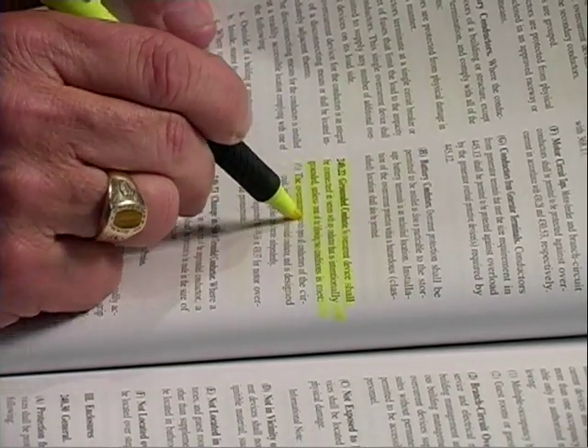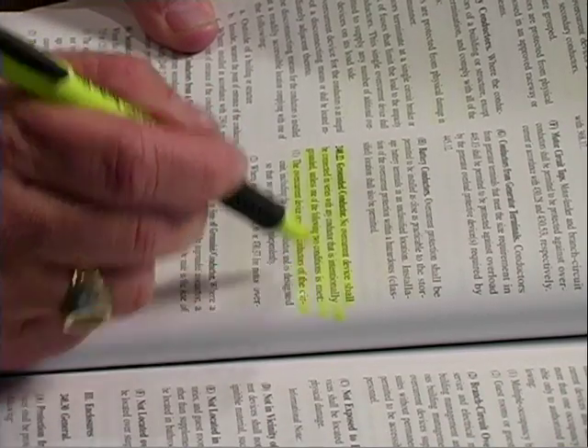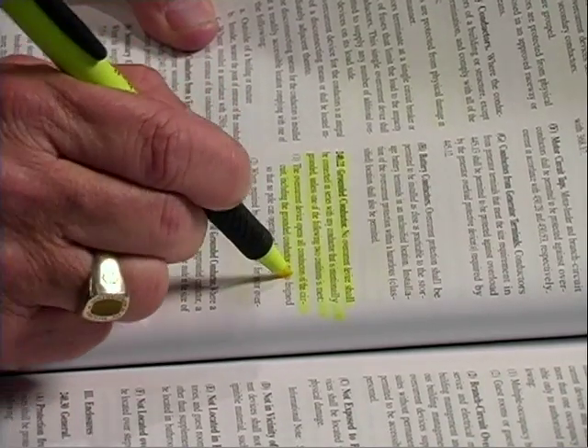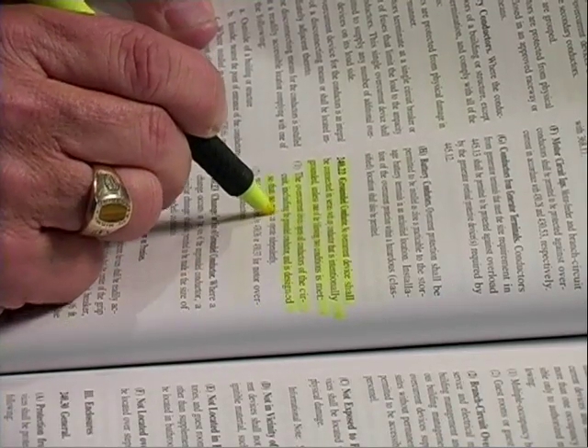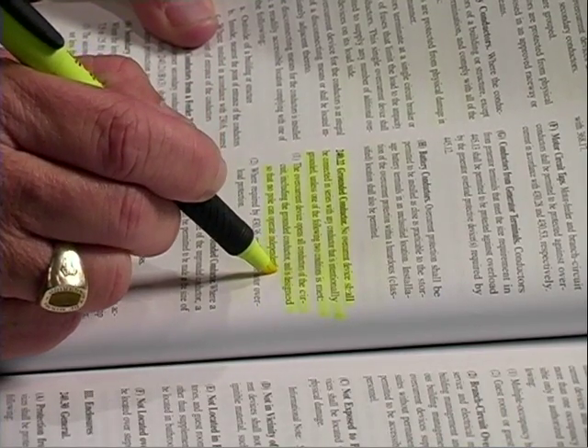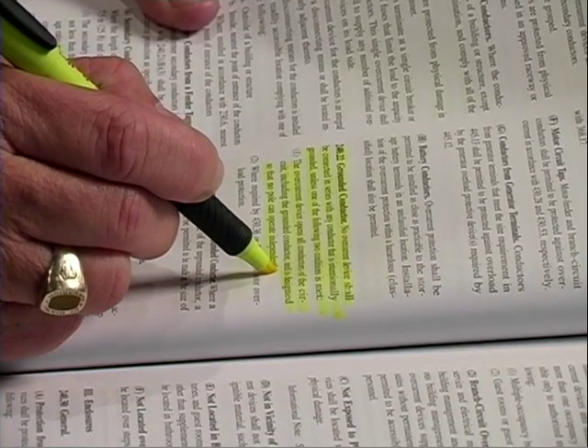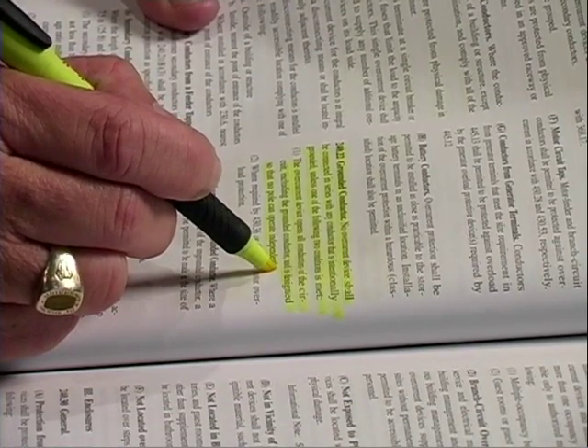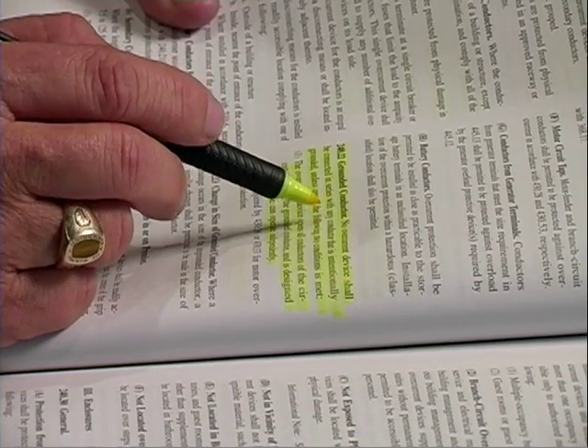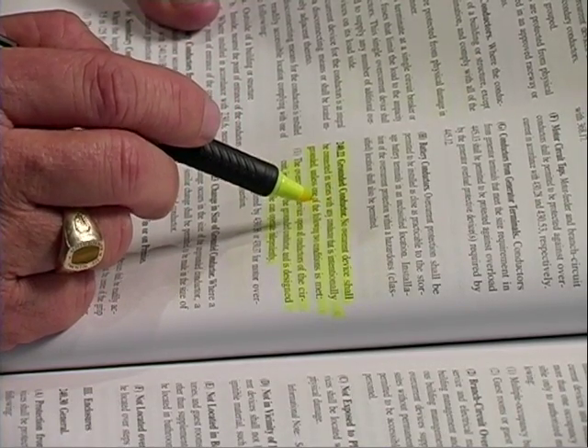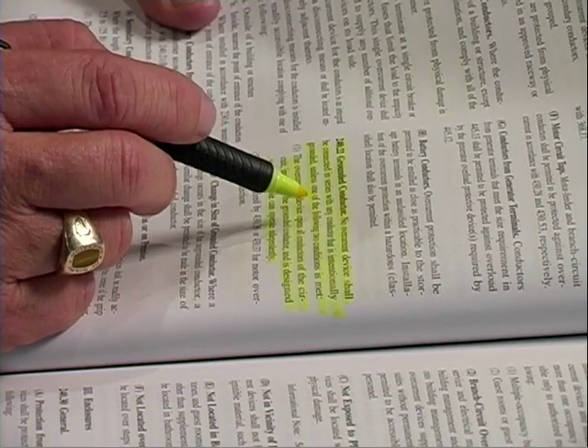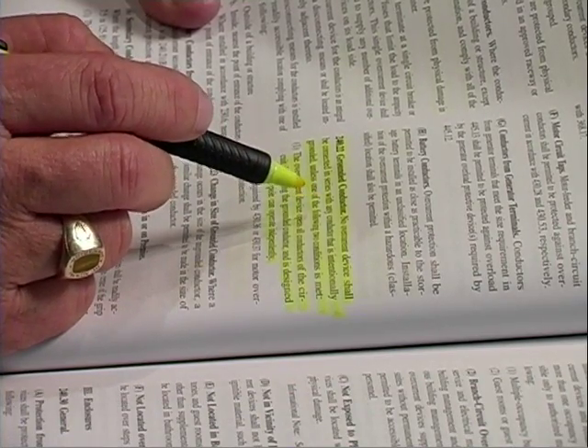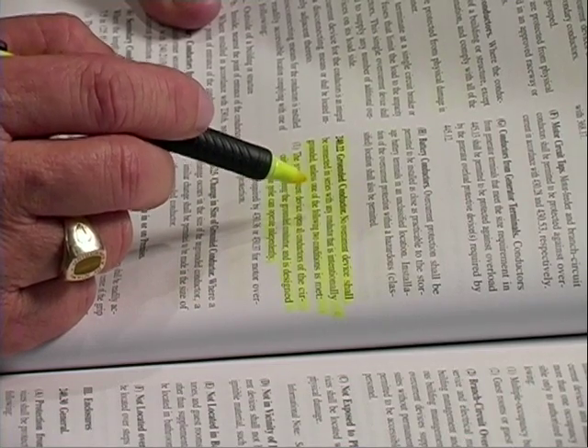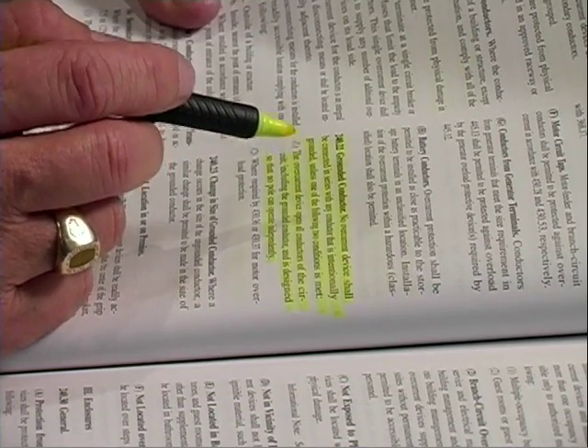Number one is the overcurrent device opens all conductors of the circuit, including the grounded conductor, and is designed so that no pole can operate independently. That means I'd have to put what then? A circuit breaker, if I plan on switching the neutral. Is that right? So I could use a 3-pole circuit breaker on a corner grounded system. One phase is going to be white, and the other 2 phases are going to be identified however we're going to identify them for the system.